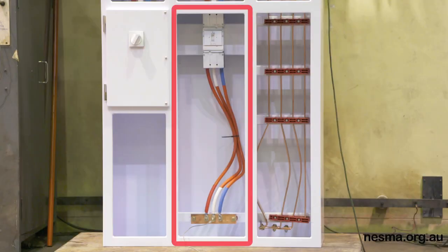Okay, second test is a bolted short circuit on the load side of a circuit breaker. I don't want to say anything wrong here, Max. Is the test one section being isolated? We're doing that? Possibly, yes. The setup is a circuit breaker mounted in its own compartment. There's no door on the front though. The circuit breaker is fed from the main bus bars. A bolted short circuit at the end of a short length of cable as required by the standard, and a test current of 50 kA for 0.2 of a second. The circuit breaker will withstand the test current and can be operated manually. We hope so. Our objective is to show pressurisation of the functional unit and the output of a circuit breaker when performing a fault clearance within its capabilities.